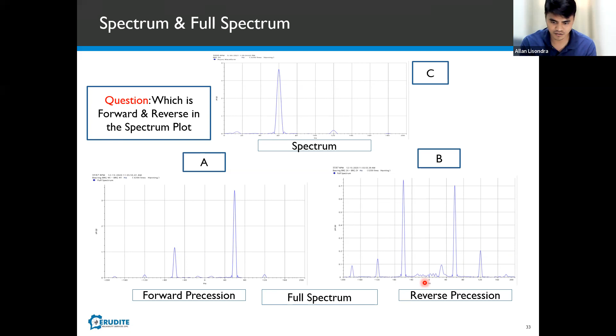This is just an example of forward and reverse. Someone may ask, what is the importance of forward and reverse? We'll discuss that later, since we'll also cover rubbing, oil whirl, and oil whip. If you have a reverse, it's mostly an indication that you have some rubbing, but not all the time — that's why you have to look at every plot or data in your system. It could also be a switching of your X and Y, maybe you installed the X on the left and Y on the right, so that's also a good indication to check.